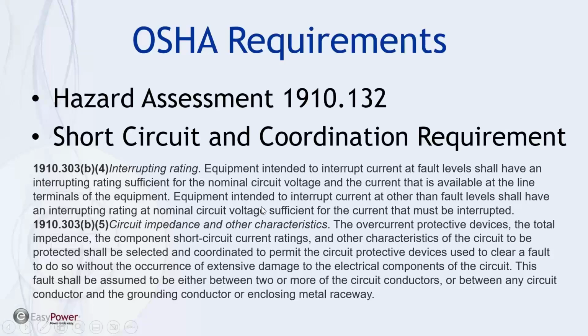And then equipment intended to interrupt current at other than fault levels shall have an interrupting rating at the nominal voltage sufficient for the current that must be interrupted. So that's the other one. So it's got a 20 amp rating that is for load, and that's other than the fault current. And then there's 10,000 amp on this breaker for fault current, and then there's the voltage rating. So all of these have to be part of the breaker.